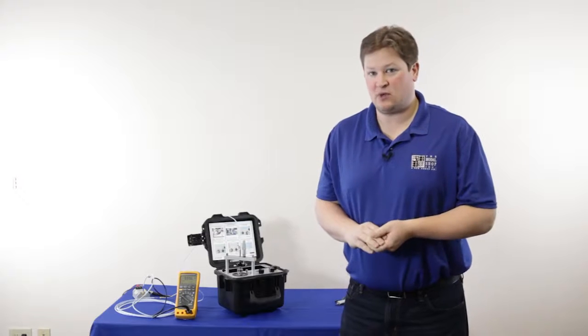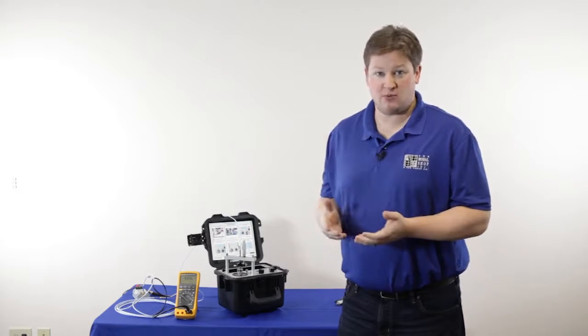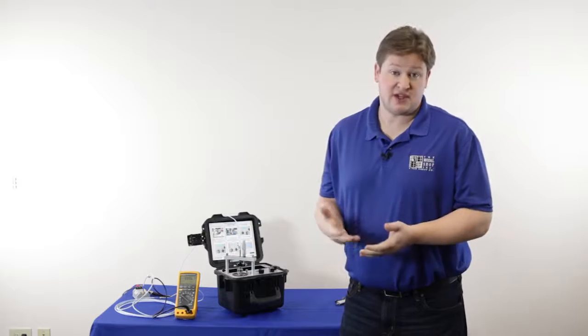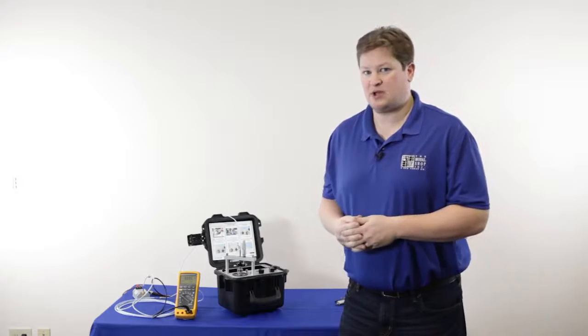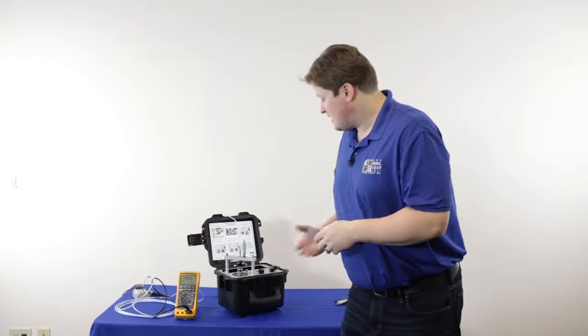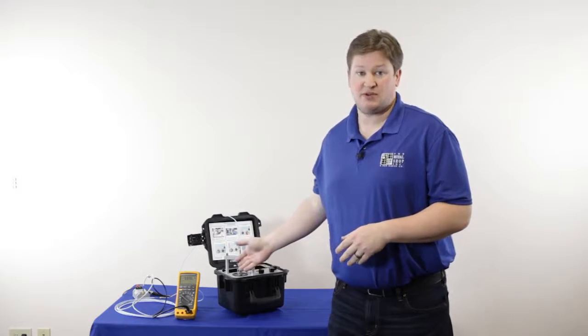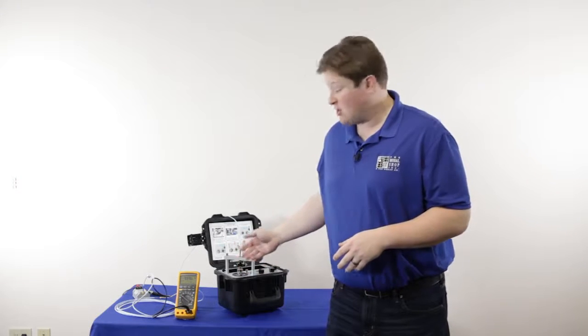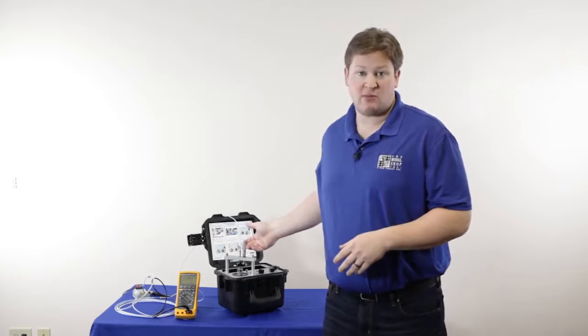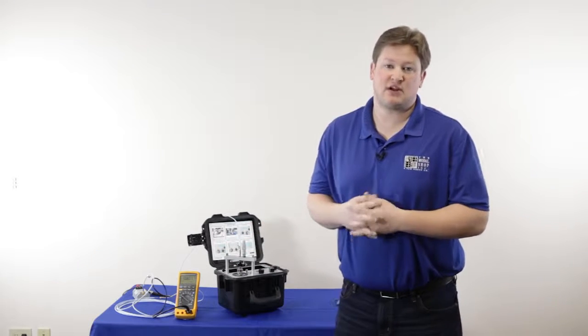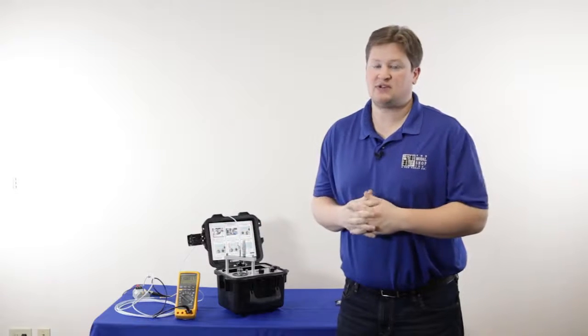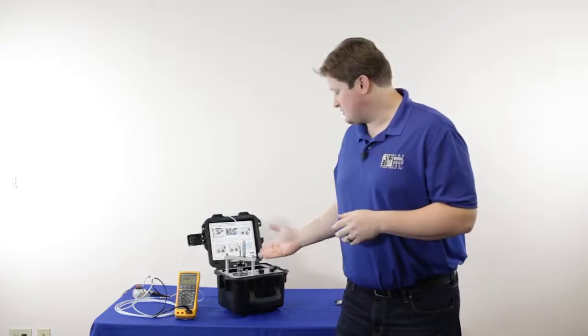So as you can see, once you become familiar with the proximity probe adapter kit and your case thread size, mounting the proximity probe becomes fairly easy, and you don't have to worry so much about the position of the probe within the bracket or even the position of the probe on the dial micrometer. Dynamic testing of the proximity probe is fairly simple once you set the proper gap voltage and use the correct mounting bracket.